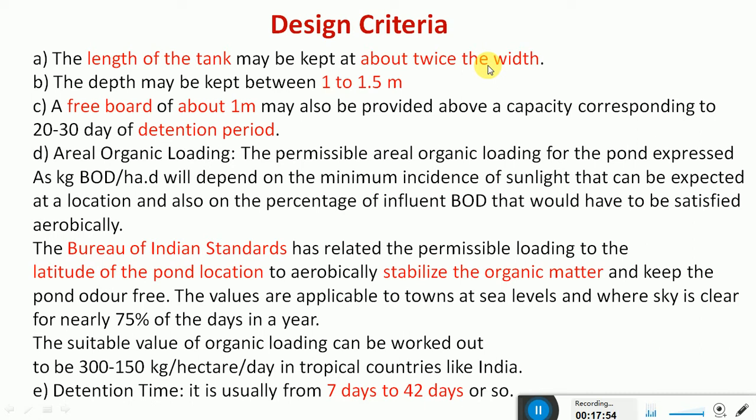Okay, so the depth may be kept between 1 to 1.5 meter. This again varies whether it is an aerobic pond, anaerobic or facultative. So based on the design the depth varies. A free board of about 1 meter may also be provided above a capacity corresponding to 20 to 30 days of detention period. Then organic loading.